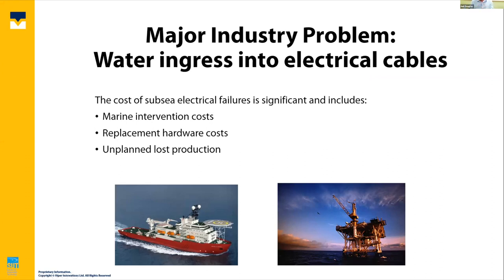As the copper is eroding, or corroding, I should say, we're effectively reducing the cross-sectional area. Each of those strands is slowly corroding and breaking, and that means the cross-sectional area of the copper keeps changing. I don't know if it started out at 6 square mil, but it keeps reducing. At some point, it's not going to be able to carry the current that is being supplied to the subsea consumers. So at some point, that cable is going to act like a fuse.